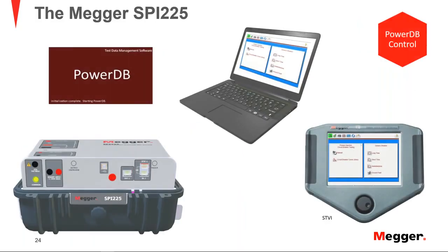The next is the software. For those that are familiar with our instruments, we use the flagship software PowerDB, which we use not only for SPI, but for many other instruments in our lineup. You can see from what I've shown you of the unit itself, it hardly has any buttons. It actually only has one button, which is the emergency stop button in the front, right here. Other than that, it has just connections to either the computer or the smart touch view interface, a USB port to connect to the computer as well, and then connections to my specimen, my output, my taps, which we'll cover in a minute, as well as a binary input if we want to monitor an extra contact.